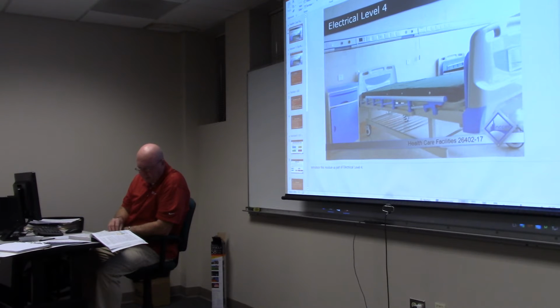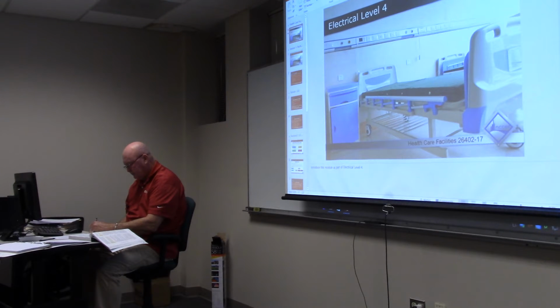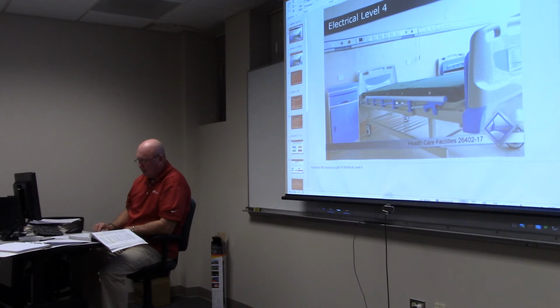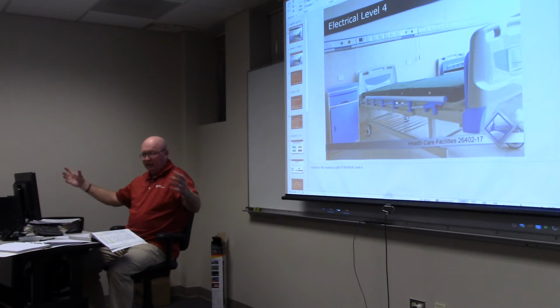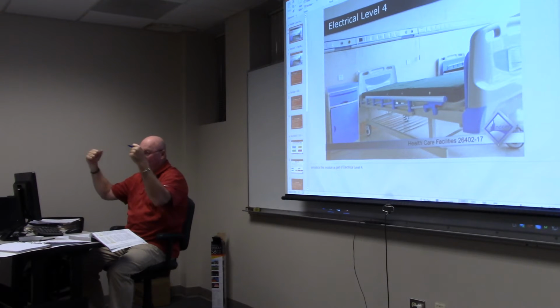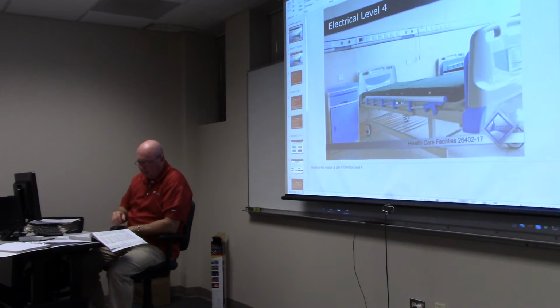All right, number 11. A double-ended substation is typically used when transformation over 750 kVA is needed. Yeah, double-ended. And that's what I was telling you earlier. I'm not too interested in y'all knowing a whole lot about that because I think it'd be rare that we'd get into that case. But double-ended, what you really got is two alternate sources of power. If one doesn't work, it goes beyond one generator. It's saying now we're going to have two. A backup to the backup. That's what we're having. All right.